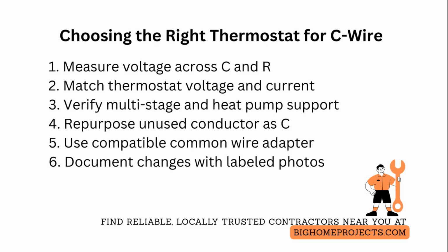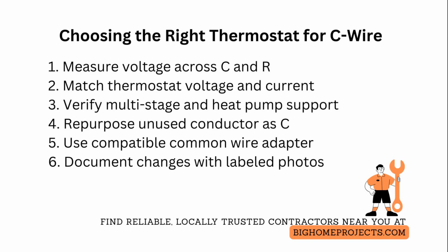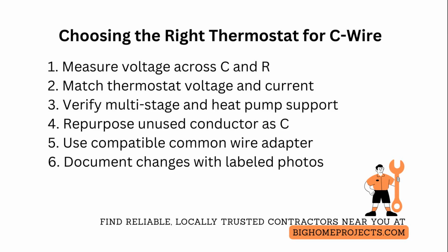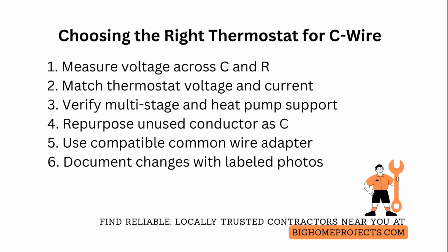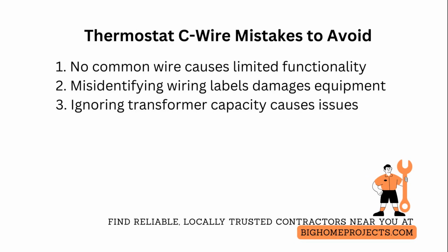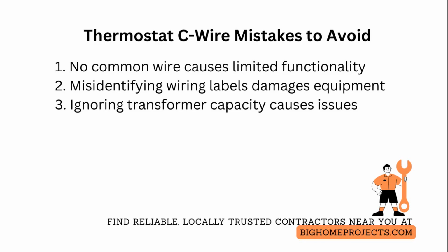Document every change with photos and label both ends of the repurposed conductor so future technicians won't disconnect the C wire accidentally. Finally, run a full system cycle test including heat, cool, fan, and any auxiliary stages after installation, and monitor the system over 24 to 48 hours for short cycling, error codes, or transformer overheat. Address those immediately.